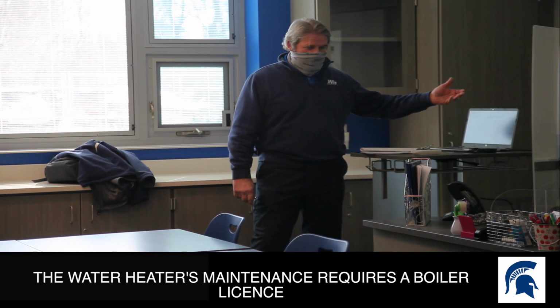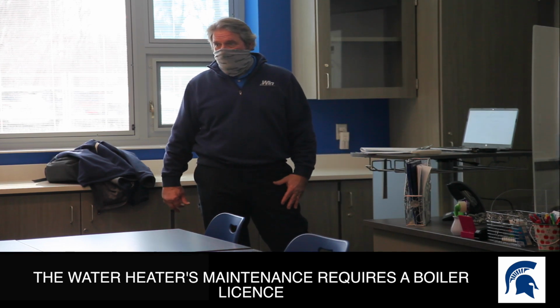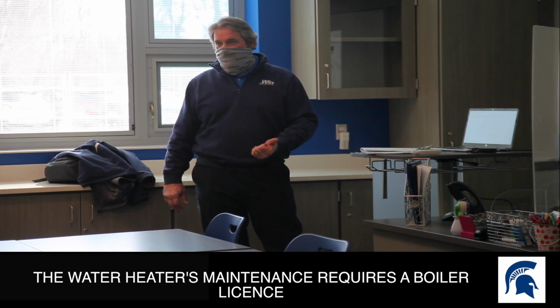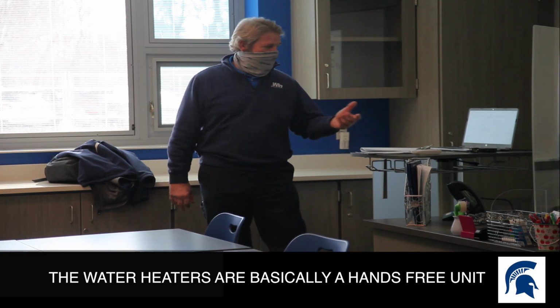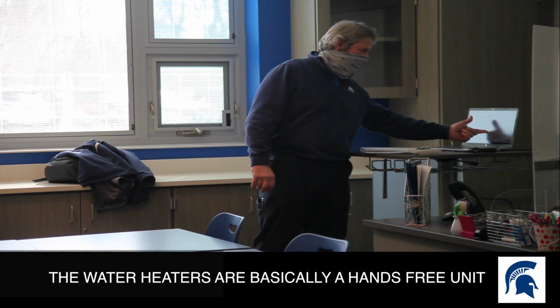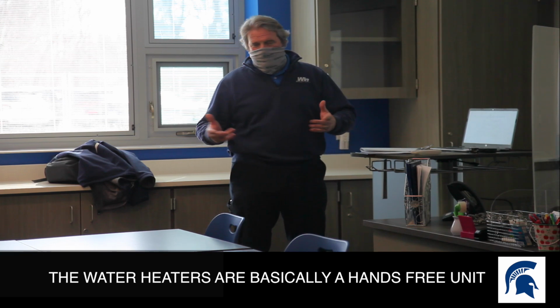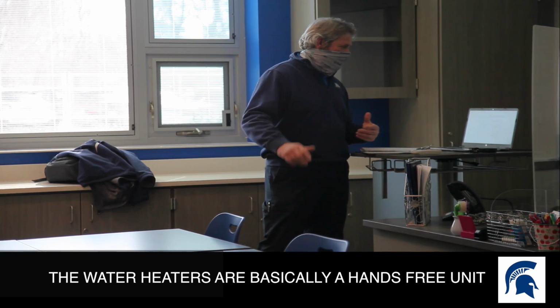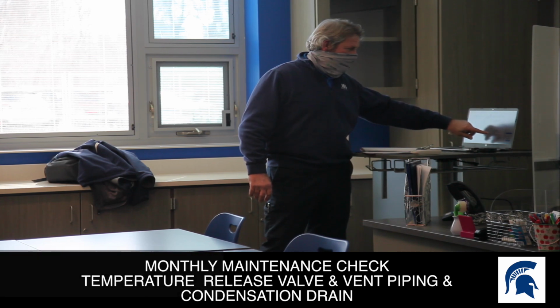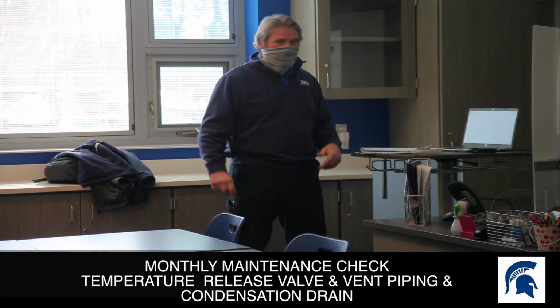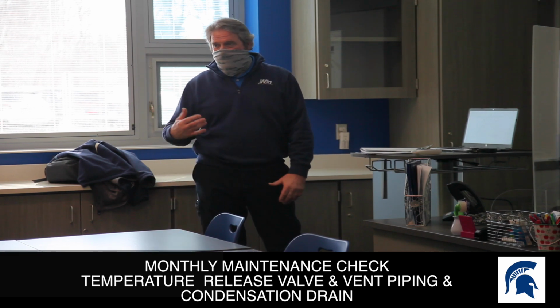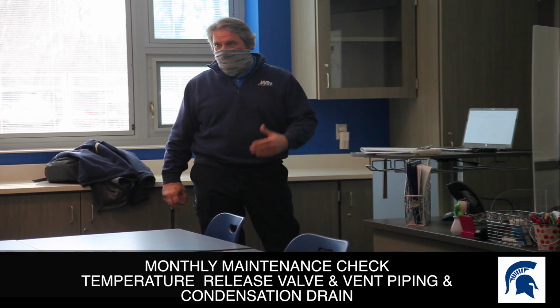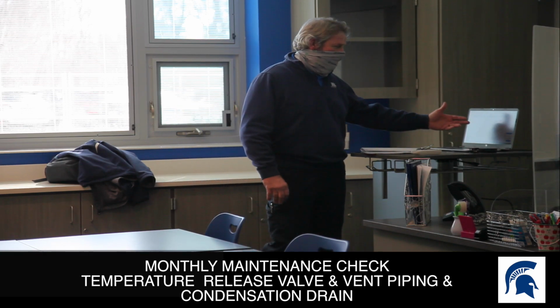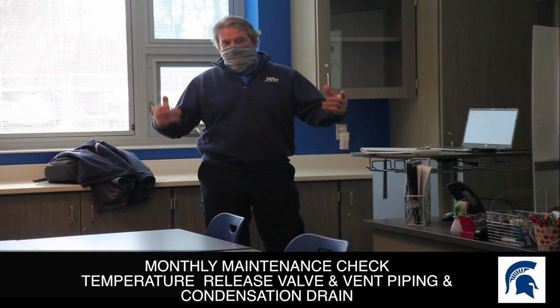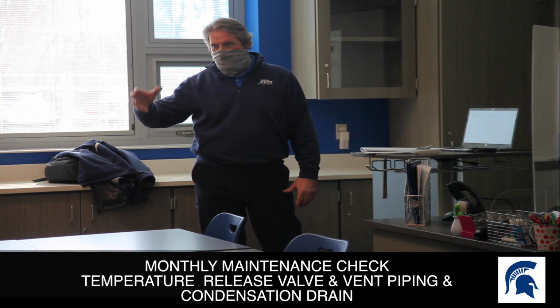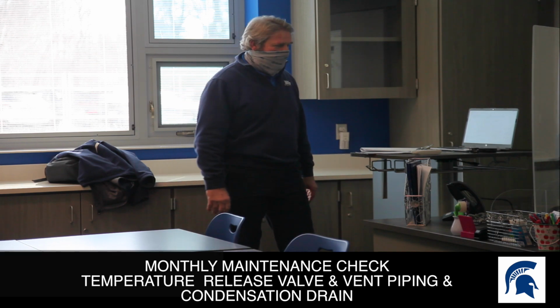So going over them, basically they should be a hands-free unit. The main thing to check on a monthly and they tell you here, monthly on the T&P and things like that. 6 months is okay, but you can absolutely do it monthly. What does T&P mean? Temperature and pressure relief valve. You open that up, make sure it's functioning, closing back up, so then you're protected with your pressure. Your vent piping, you're just going to manually look, make sure no birds are making nests on your exhaust, things like that. Keep an eye on that.